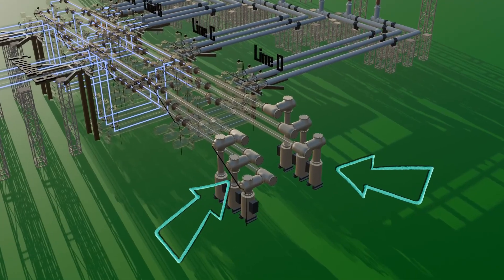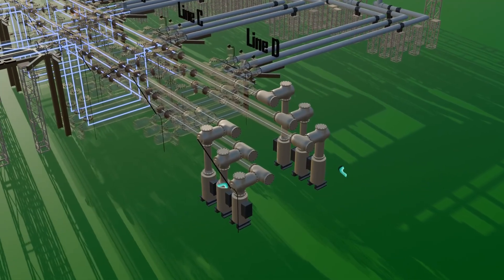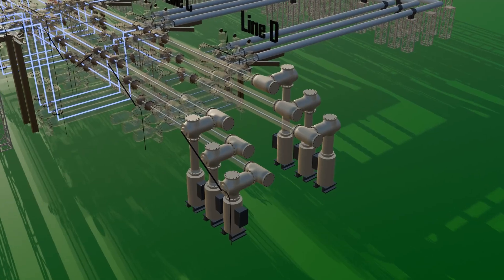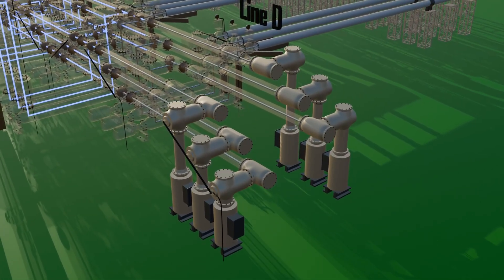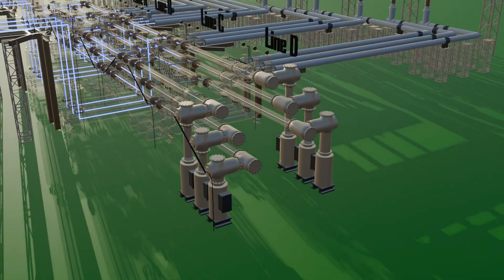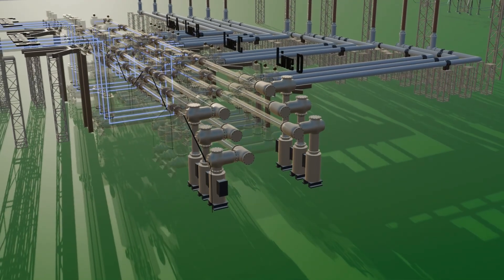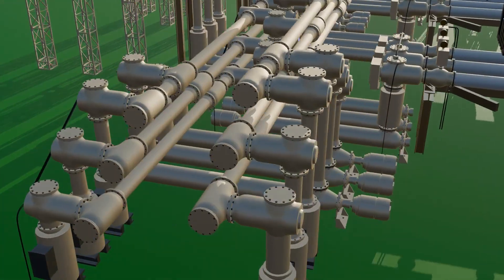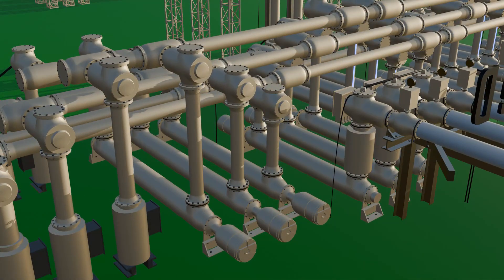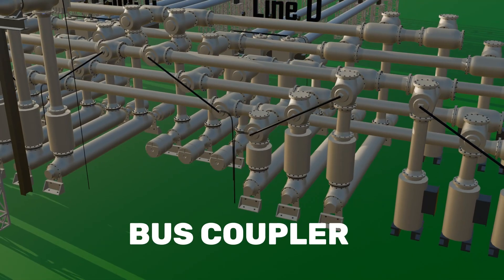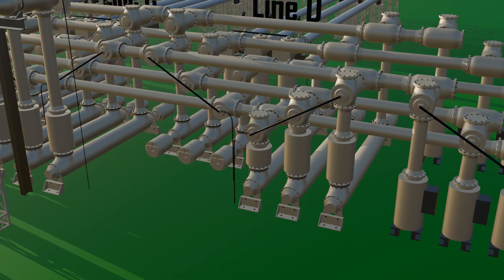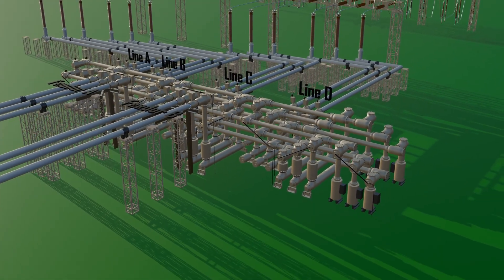For systems of 132 kV or below, a voltage transformer is used instead. Both CVT and VT are connected in parallel with the line. Sometimes both buses need to be connected together to share or balance the load. For this purpose, a bus coupler is used. The bus coupler also contains a circuit breaker, CT, and isolators in its arrangement. This is how a switching substation manages load.